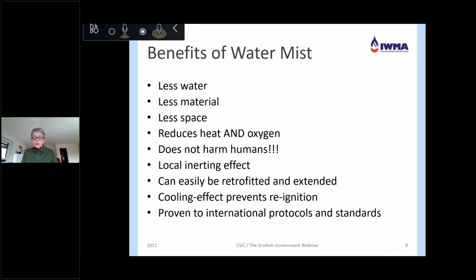Due to the size of the droplets, water mist is well distributed and fills many nooks and crevices within seconds of activation. It can be carried around with the airflow and is therefore not dependent on hitting the fire directly, so it's able to control or extinguish even concealed fires.